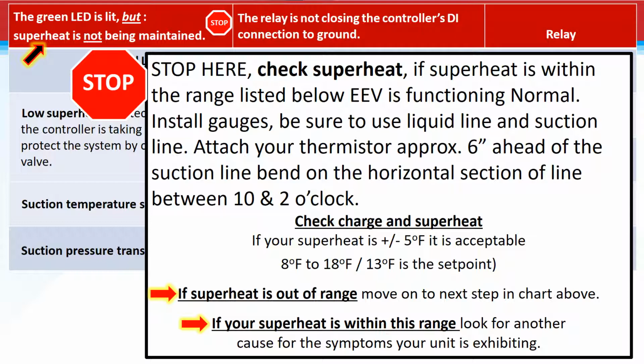Let's install some gauges. Attach your thermistor approximately 6 inches ahead of the suction line bend before the compressor so we can get a temperature measurement, and be sure you put it between 10 and 2 o'clock. Check your charge and your superheat. If the superheat is out of range, move on to the next step in the chart. If your superheat is within range, look elsewhere for the cause of the symptoms your unit has because the EEV system is functioning properly.